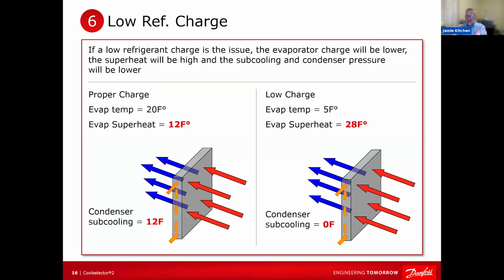When you're looking at superheat and evaporator temperature, you're only looking at the evaporator. You're taking a snapshot of what's going on in the evaporator. That just tells you don't have enough refrigerant in the evaporator for your load. That's the first thing I mentioned when I mentioned superheat. Subcooling, on the other hand, that takes place way over there in your condenser. That determines your charge. All right. Yeah. For an adaptive device, you mentioned EEV and TXV. Those are two adaptive devices that we're talking about here. Yeah.